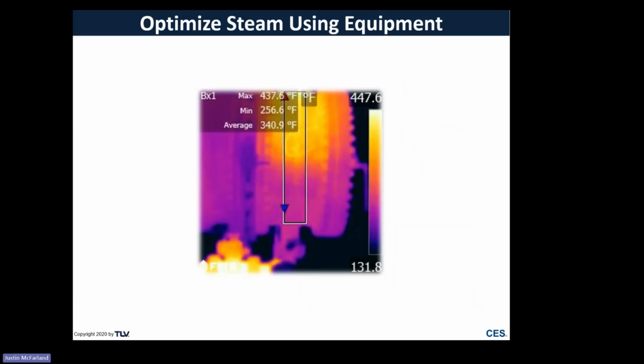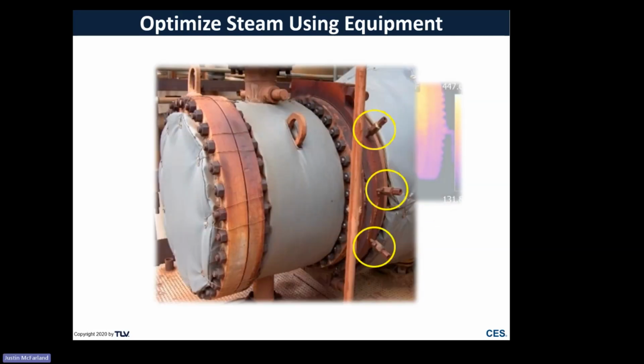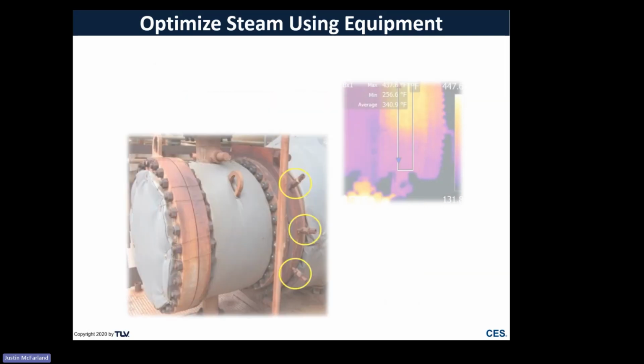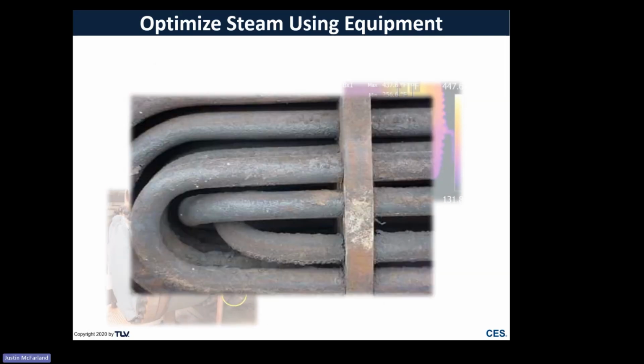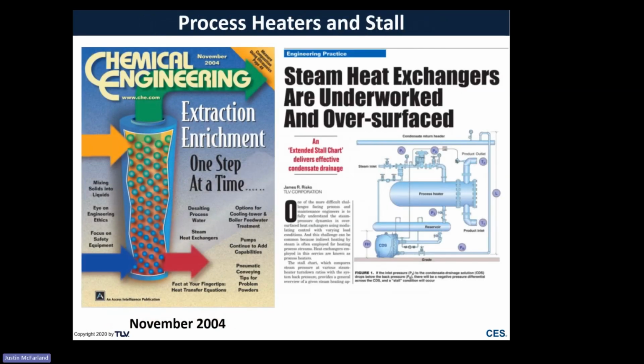So what we don't want to see are things like temperature stratification. So it's the channel head of a shell and tube heat exchanger. You can see where it's bright orange at the top, purple down at the bottom. So a big temperature gradient there. Don't want to see things like collars on channel heads that were put in place because of steam leaks at the gaskets. Don't want to see things like corrosion or fouling on the tube bundles. So all those things are problematic. All those things are things that we're going to be talking about as to some of the things that we want to mitigate with our process equipment.